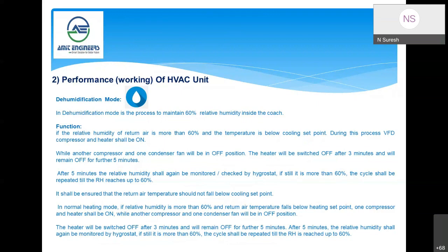Say, for example, even in coastal areas, the temperature outside will be less, but the humidity will be very high. So without the heater, if we run both compressors, or even one compressor, continuously, the dry bulb temperature may come down quickly. That is basically sensible heat. Whereas the wet bulb temperature will not come down so quickly, it will take some time. Meanwhile, the dry bulb temperature will go to a non-desired temperature. Say, for example, the grill outlet temperature may go less than 10 degrees also.